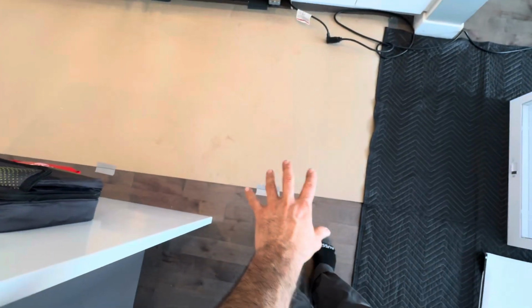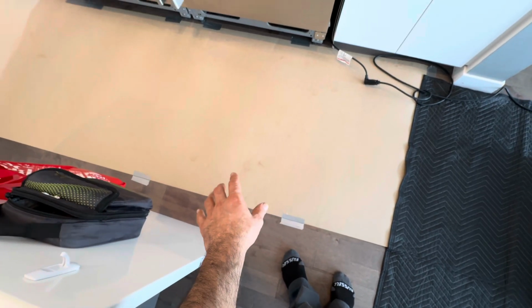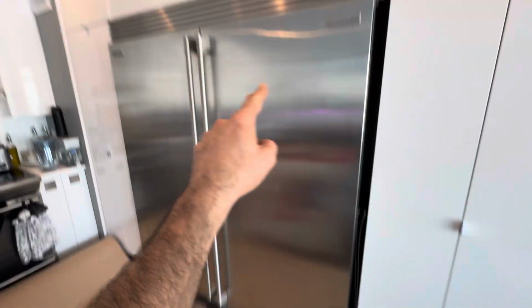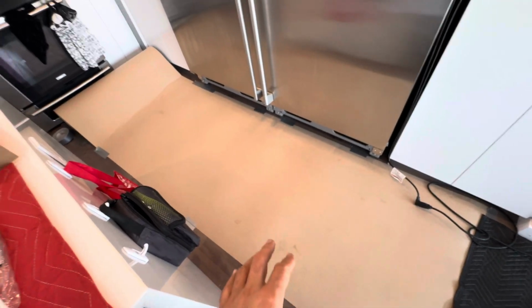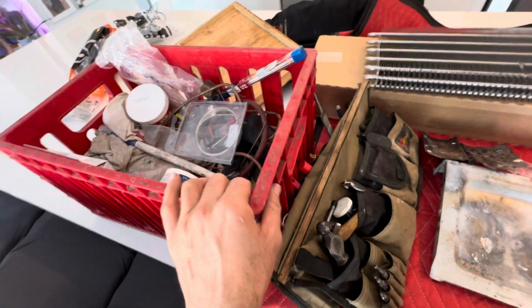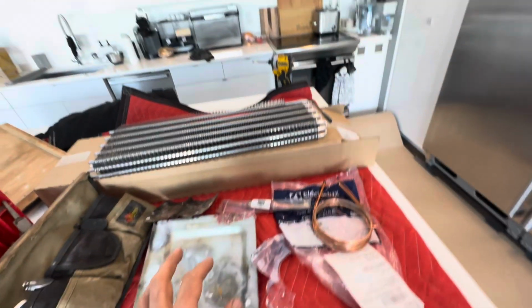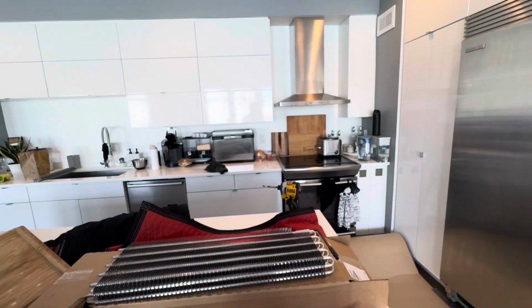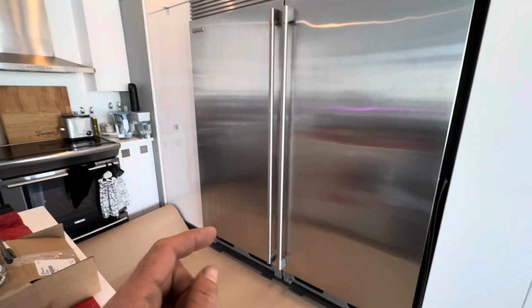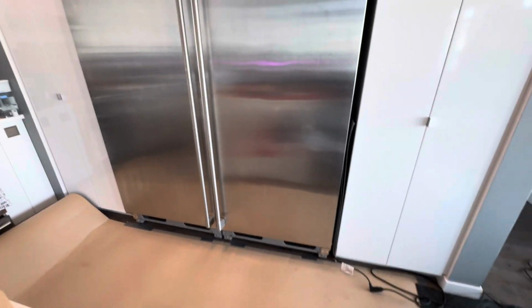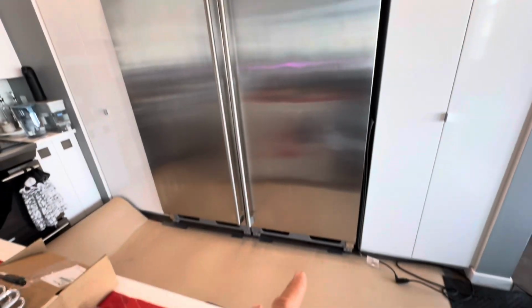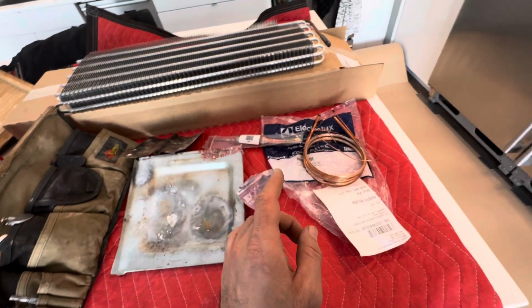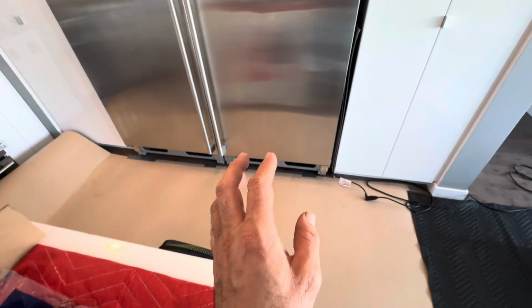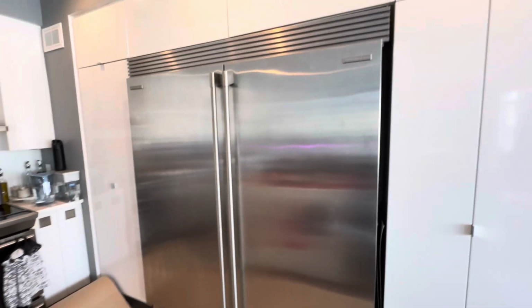You have to prepare your flooring protection here. I have ram board that I use in front of the unit. The trim piece comes out, and then you pull the unit out and work on it from there. Of course, you will have all your refrigeration equipment in here. You also want to make sure that you ask the customer if they have a carbon monoxide or smoke detector that may go off. If it's going to call the fire department, you may want to talk to them to disable it before you start your work, because you're going to have some smoke, and you do not want the fire department showing up at the customer's house.